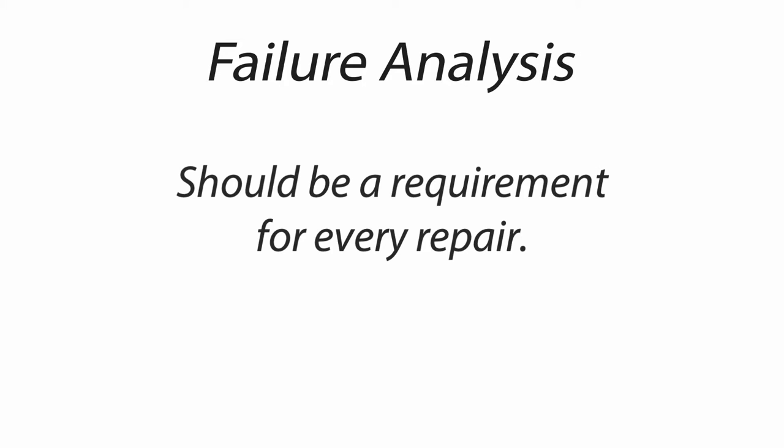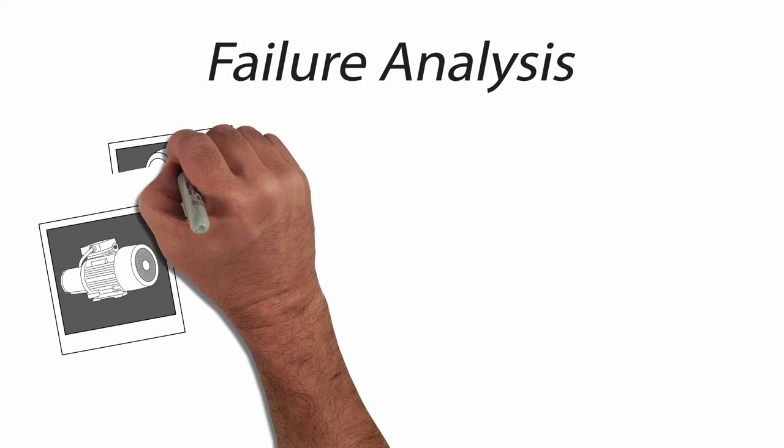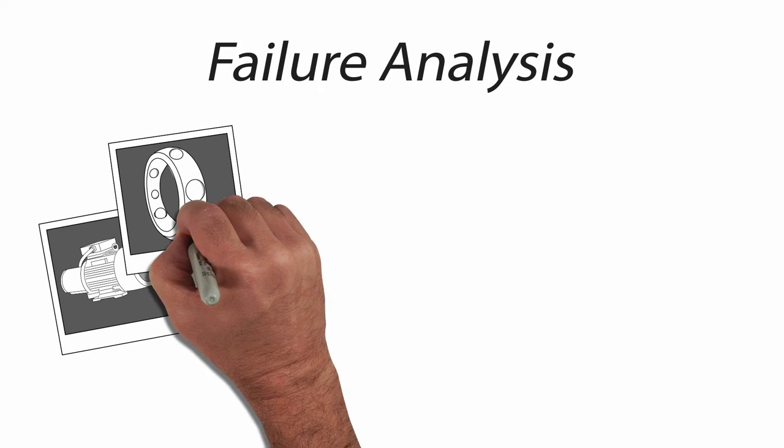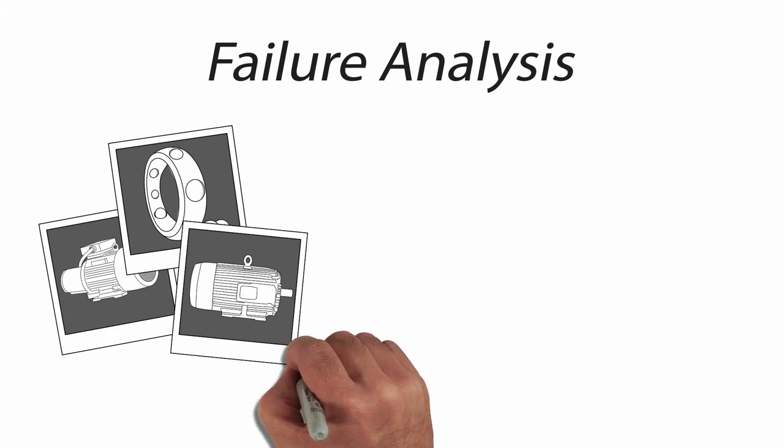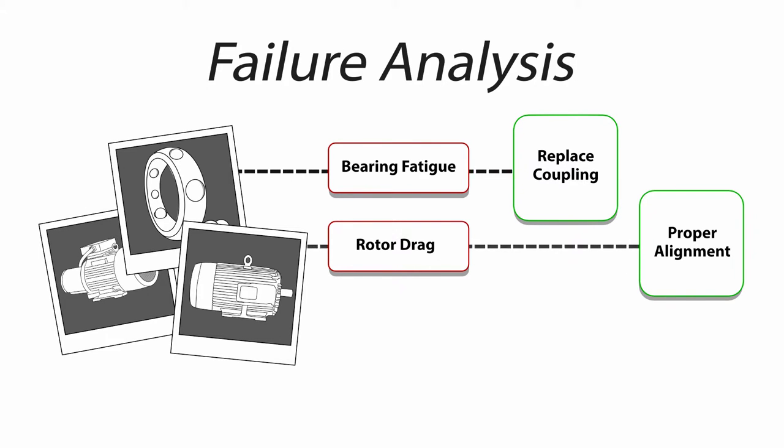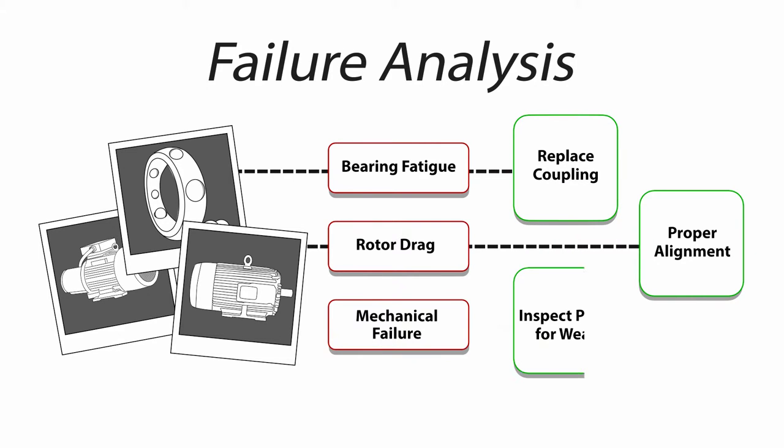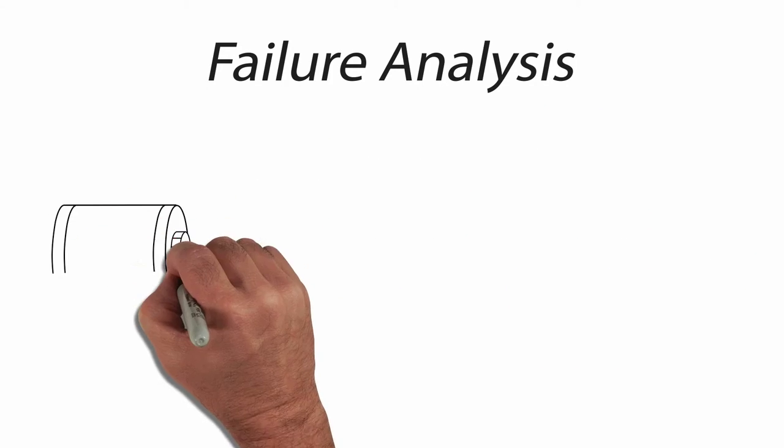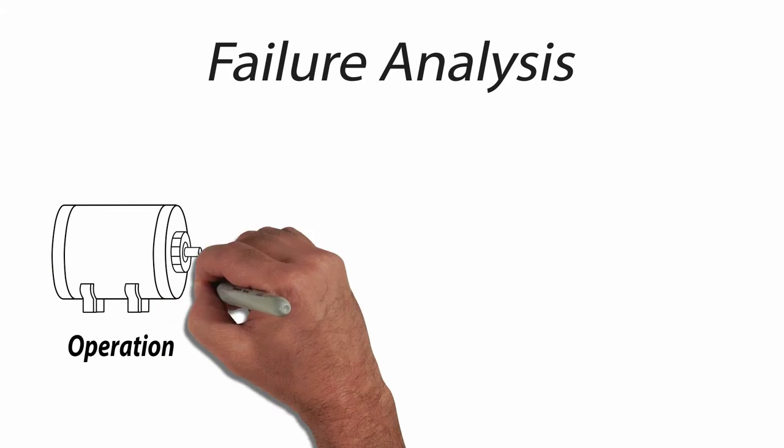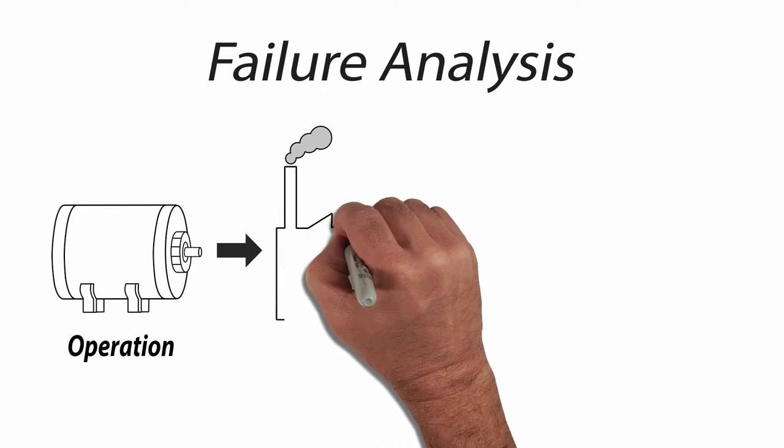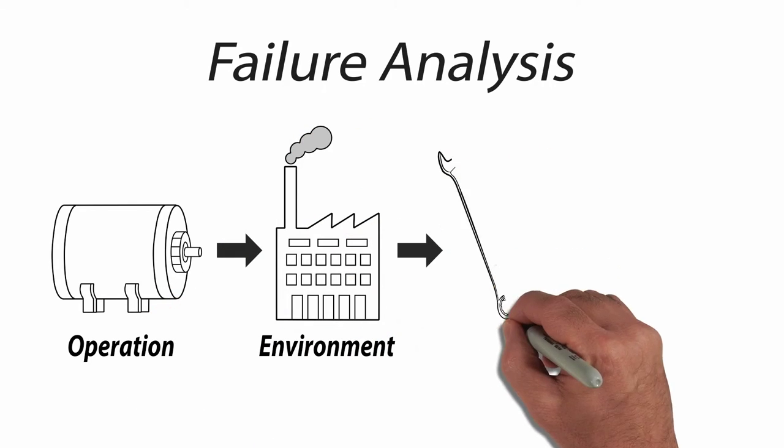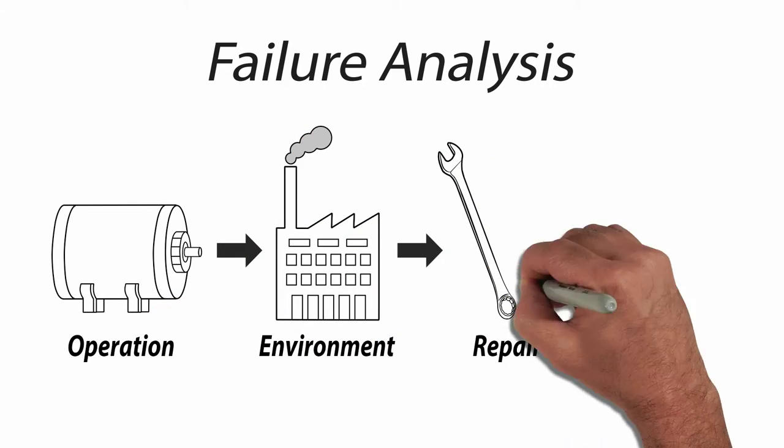A failure analysis should be a requirement for every repair. Have your motor shop capture photos, categorize failure types, and provide suggestions on how to prevent failure. This is critical to finding improvement opportunities in the operation, environment, or repair process itself.